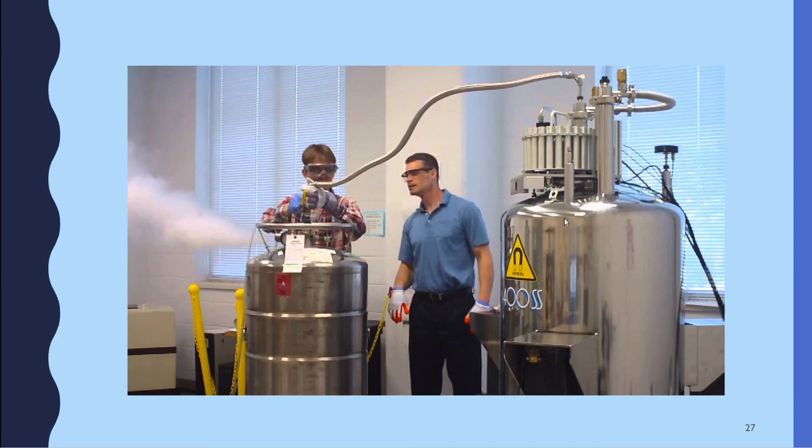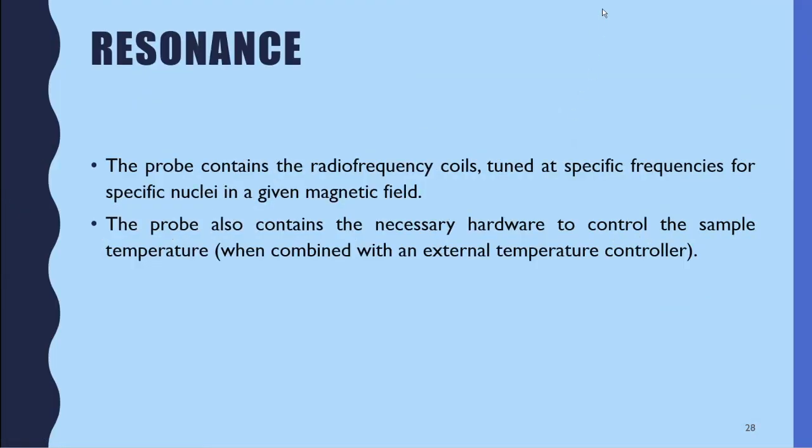and so this is an example where the people in the lab are refilling this. I don't have the picture of our own people refilling, so hopefully one day I get to take our own people's pictures of them refilling the gas, the liquid nitrogen, liquid helium.